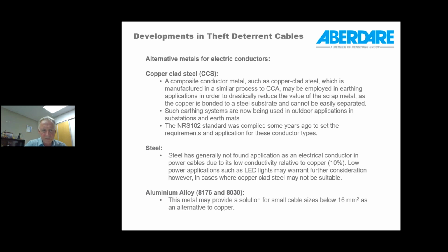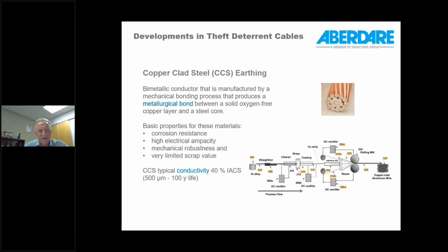Aluminium alloy. These 8176 and 8030 alloys were specially developed in America years ago, and these alloys are used for wiring of premises in the USA. So this addresses the problem with creep, or metal flow, leading to loose connections in electrical installations for sizes below 16 square millimeter. And that's definitely an option as an alternative to copper for these small sizes.